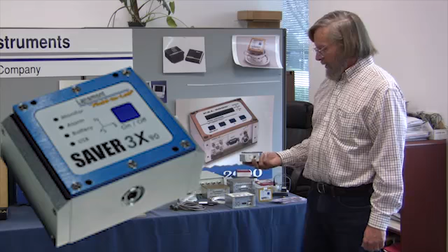Probably one of our newer instruments, it's actually been around quite a few years now, the 3X90. First instrument we came out with, as far as I know, that had USB communications, up to 128 meg data, and it'll run for 90 days on 2 9-volt batteries.